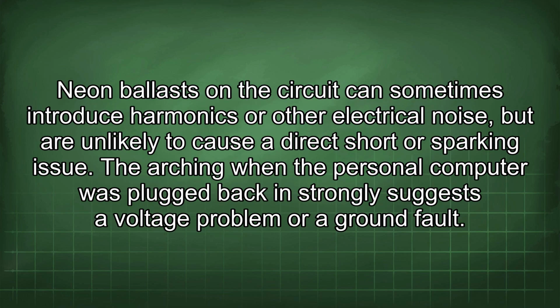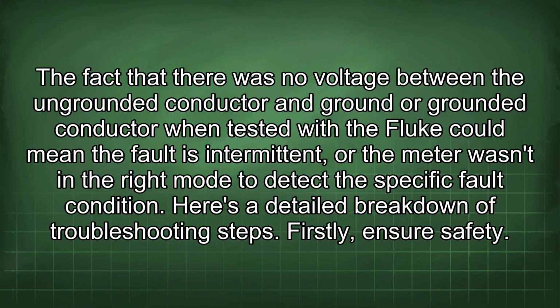Neon ballasts on the circuit can sometimes introduce harmonics or other electrical noise, but are unlikely to cause a direct short or sparking issue. The arcing when the personal computer was plugged back in strongly suggests a voltage problem or a ground fault. The fact that there was no voltage between the ungrounded conductor and ground or grounded conductor when tested with the Fluke could mean the fault is intermittent, or the meter wasn't in the right mode to detect the specific fault condition. Here's a detailed breakdown of troubleshooting steps.